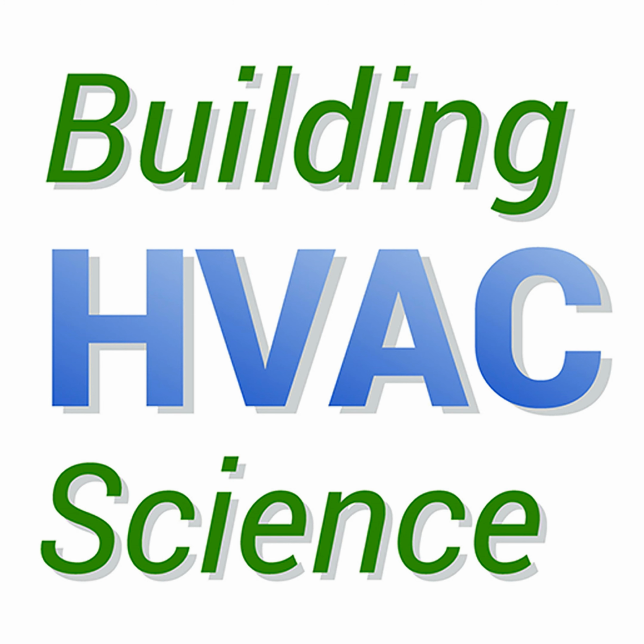That's interesting. This could be a good solution for somebody that wants to go to a heat pump but doesn't necessarily have a 200 amp panel. They might be able to run this off a 100 amp panel because you don't have to have the HVAC unit plus a water heater plus all the other stuff running simultaneously. That's right, sometimes you need to do all the cable upgrades and stuff, which costs so much money.